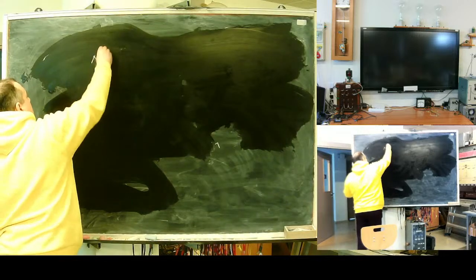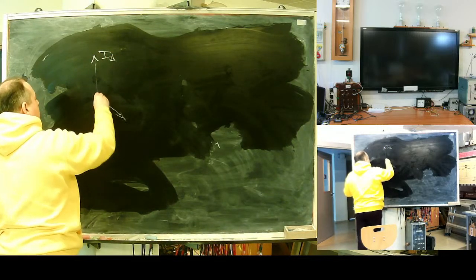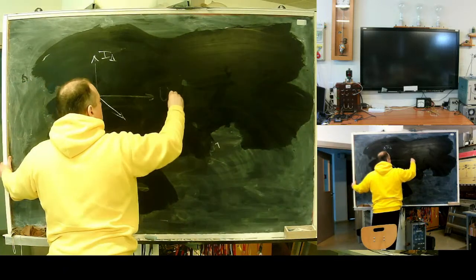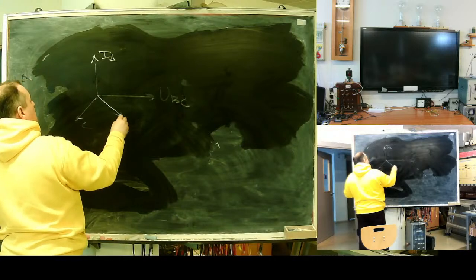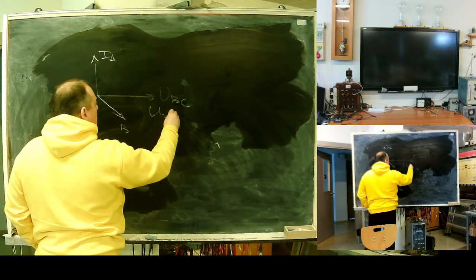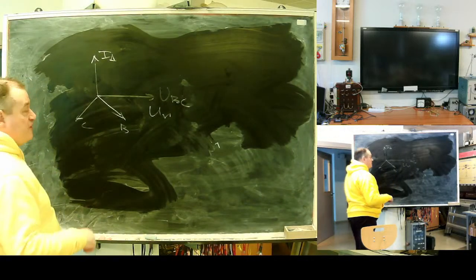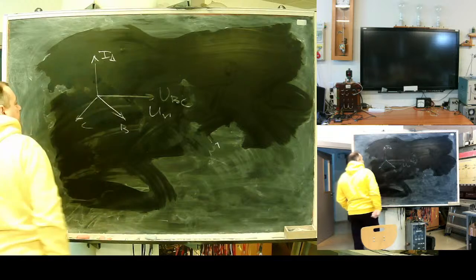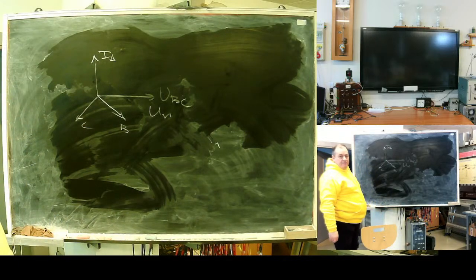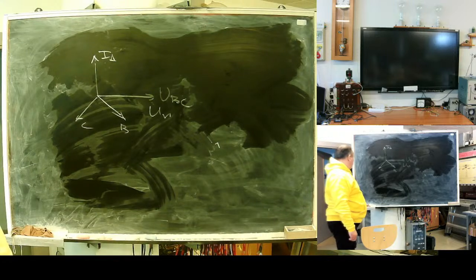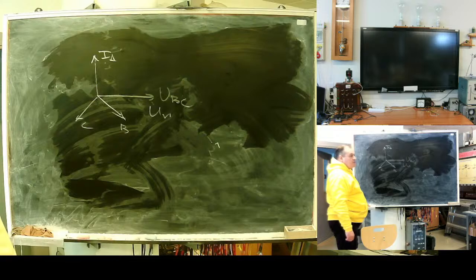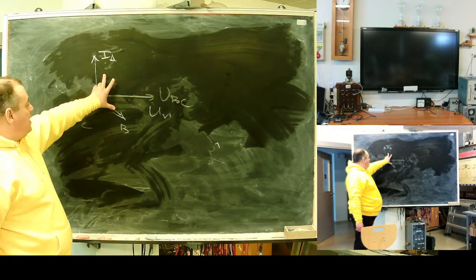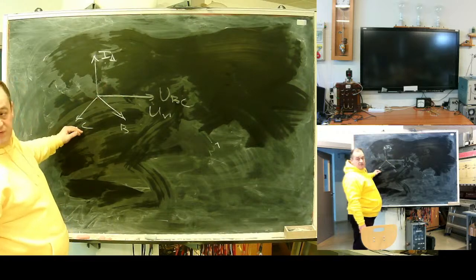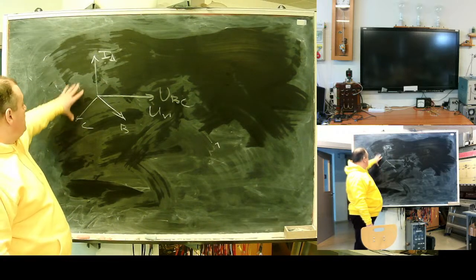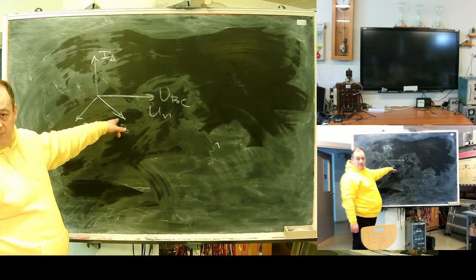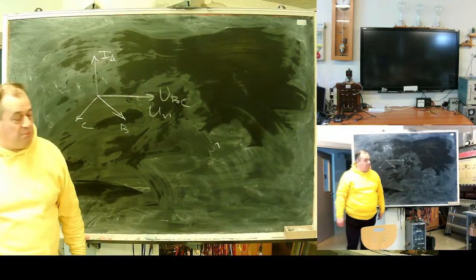The idea: take BC as relay voltage, I'm calling A phase relay, and this current as relay current. Such connection is selected for reliability. In case of AB fault, C-phase voltage, third phase voltage will remain. In case of AC, B-phase voltage will remain. Such relay is much more reliable.